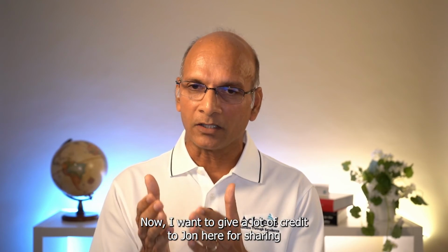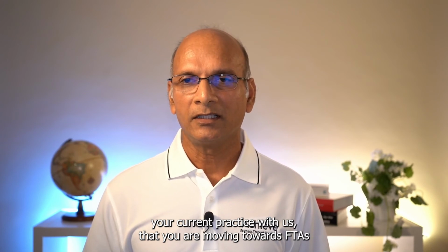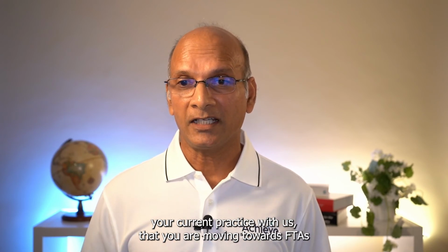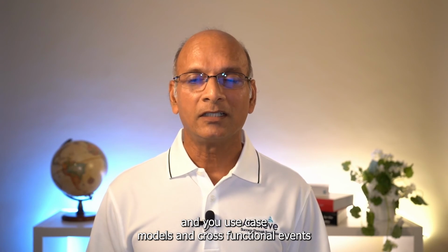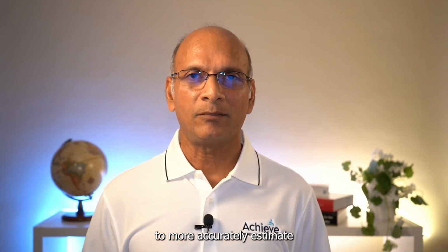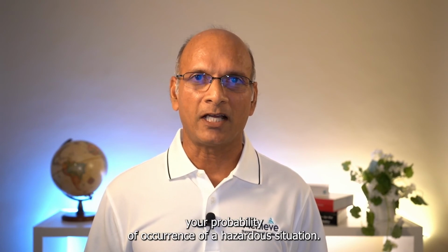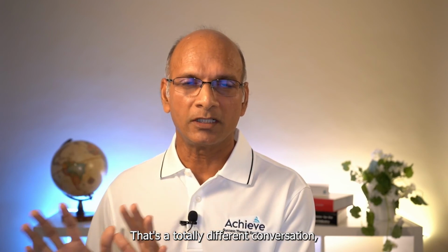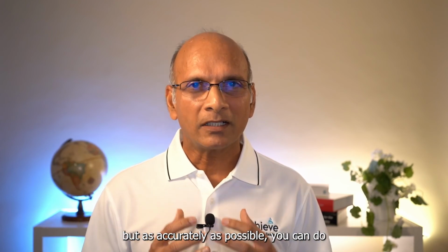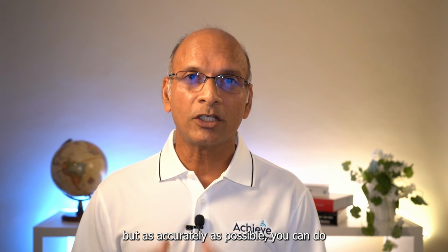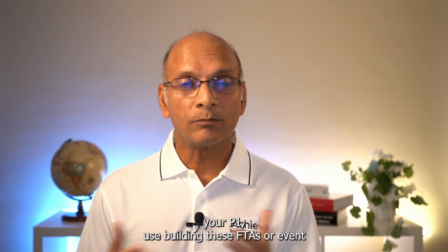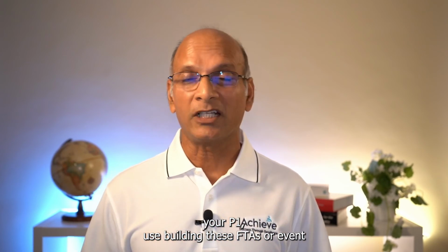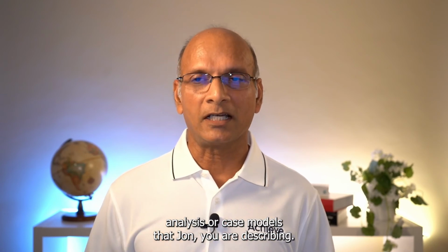Now, I want to give a lot of credit to John here for sharing your current practice with us, that you are moving towards FTAs and you use case models and cross-functional events to more accurately estimate your probability of occurrence of a hazardous situation. We have not talked about P2. That's a totally different conversation. But as accurately as possible, you can do your P1, building these FTAs or event tree analysis or case models that, John, you are describing.